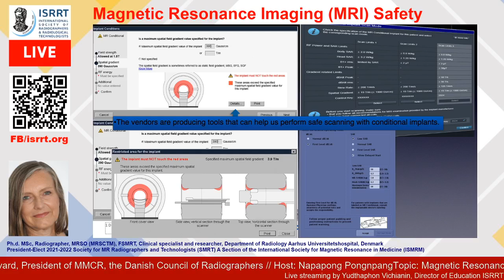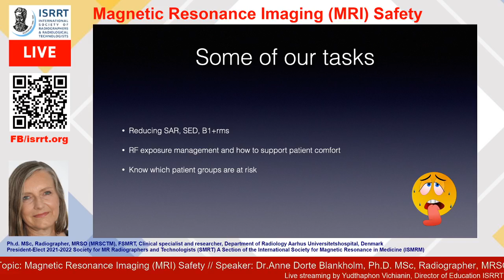One of our tasks as radiographers and technologists is to be able to reduce the SAR, SED and B1 plus RMS. And that's all about RF exposure management and how to support patient comfort. And it's also about knowing which patient groups are at risk of getting overheated. So how do we reduce SAR? On some scanners, we may even be capable of choosing low SAR mode. And that's a really great idea, because then some of the job's already done for you. The scanner then may change several parameters, but without impairing the image quality too much.